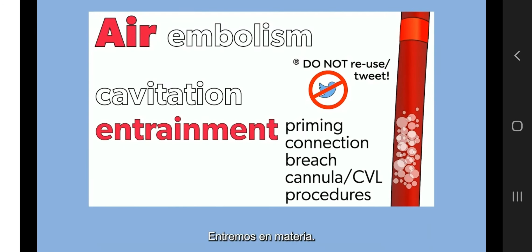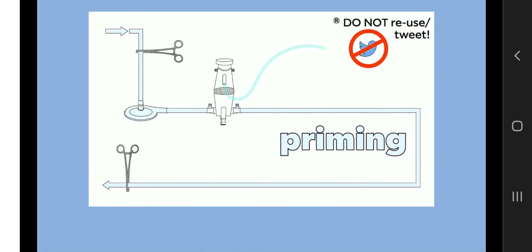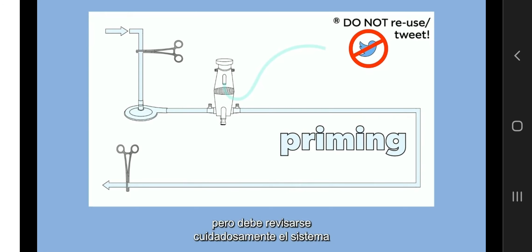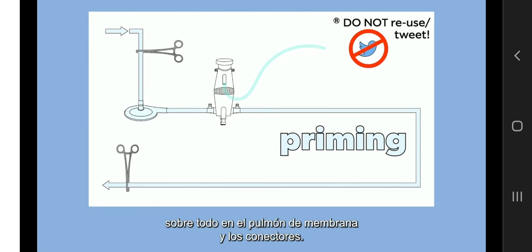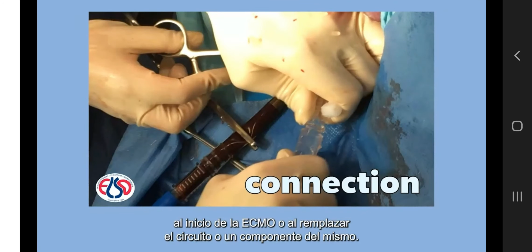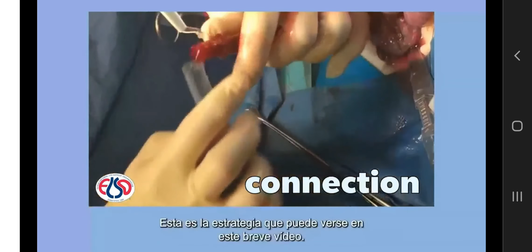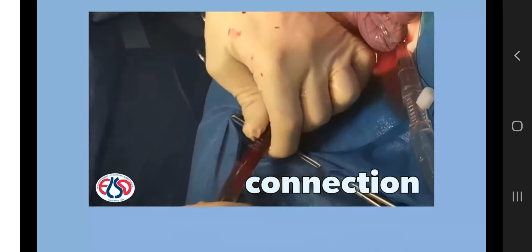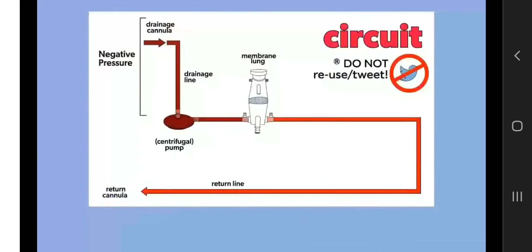Let's go into details. Air might be present in the circuit due to improper priming. Modern circuits are usually really quick and easy to prime, but carefully check the system as residual bubbles may be trapped, particularly in the membrane lung and in connectors. Air could enter at connection of the circuit to the cannulae at ECMO initiation, or when you replace the circuit or a circuit component. To prevent this risk, all connections are usually performed with a technique named underwater seal. This is the strategy that you could see in this short video.